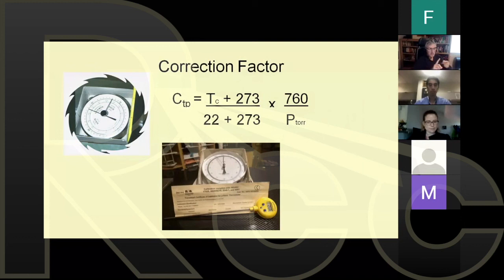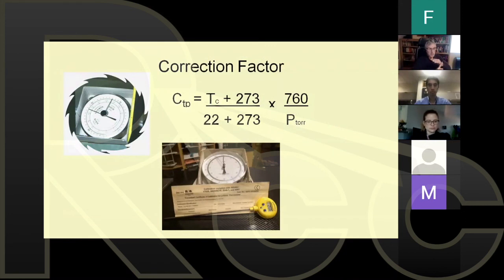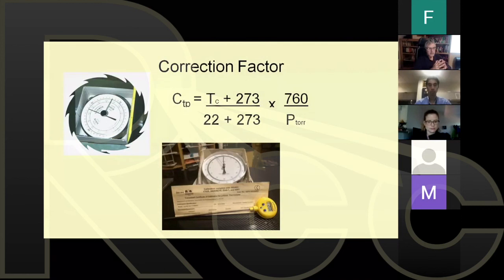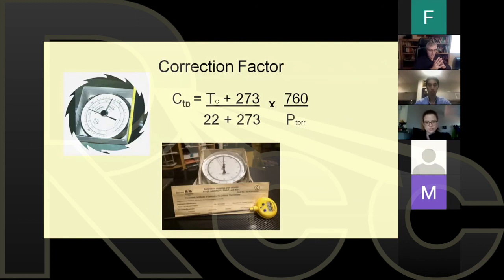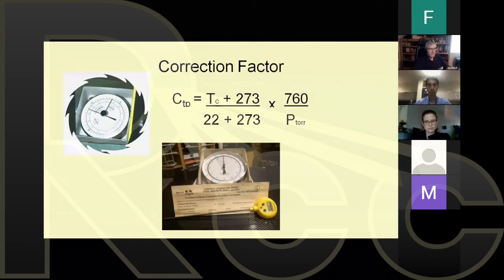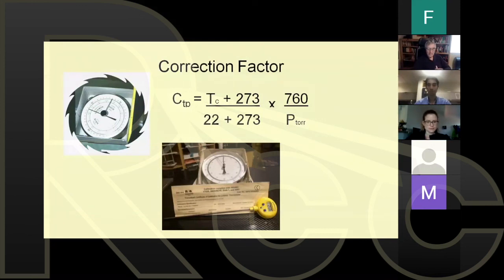The right chamber, the right depth, the right SSD, the right field size, the number of MU. There has to be a consistency there. And I find in my practice that I use an Excel spreadsheet where I have all the factors listed, and I put my numbers into that spreadsheet, and that gives me my reading in centigray per MU. But those are just a few of the very important things to look at when you do a chamber calibration. Does that help answer the question?